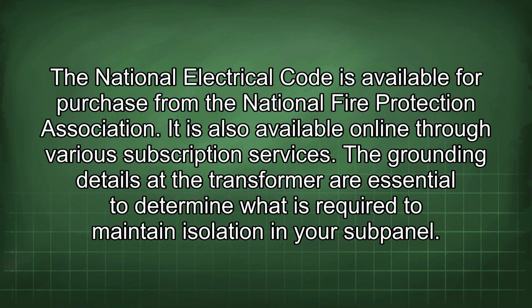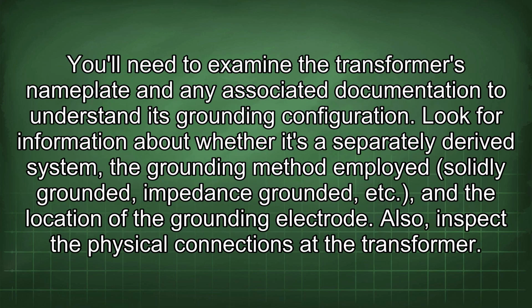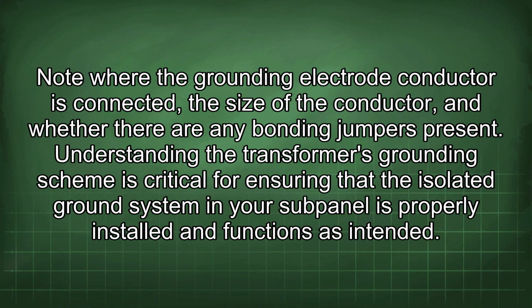The grounding details at the transformer are essential to determine what is required to maintain isolation in your subpanel. You'll need to examine the transformer's nameplate and any associated documentation to understand its grounding configuration. Look for information about whether it's a separately derived system, the grounding method employed, solidly grounded, impedance grounded, etc., and the location of the grounding electrode. Also, inspect the physical connections at the transformer. Note where the grounding electrode conductor is connected, the size of the conductor, and whether there are any bonding jumpers present. Understanding the transformer's grounding scheme is critical for ensuring that the isolated ground system in your subpanel is properly installed and functions as intended.